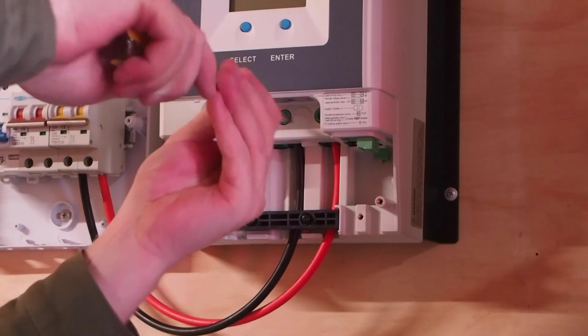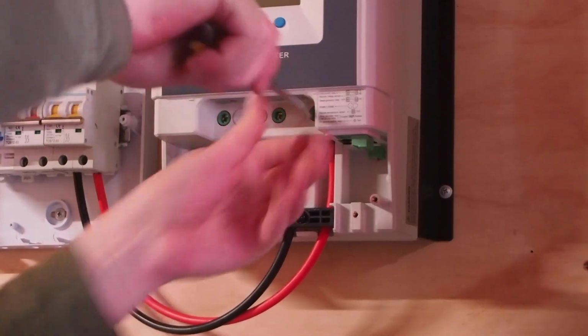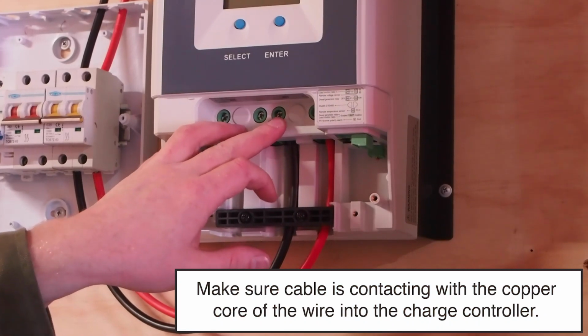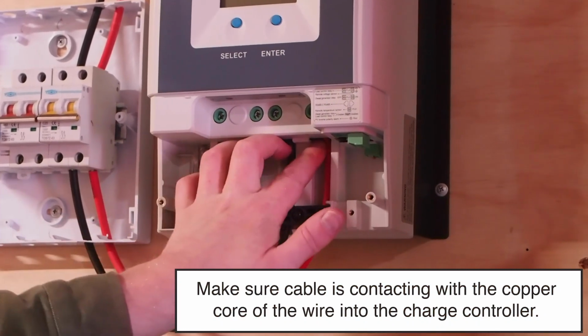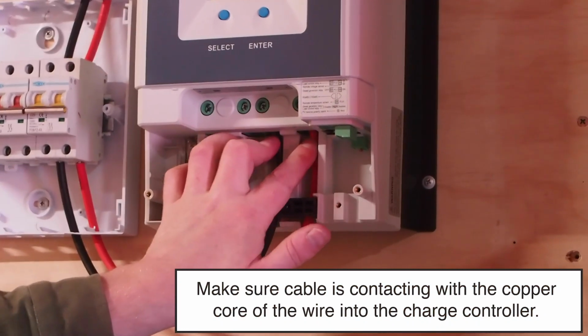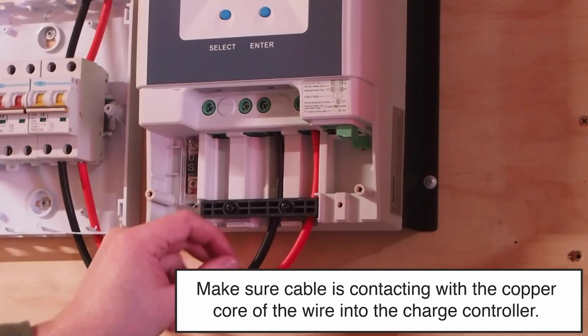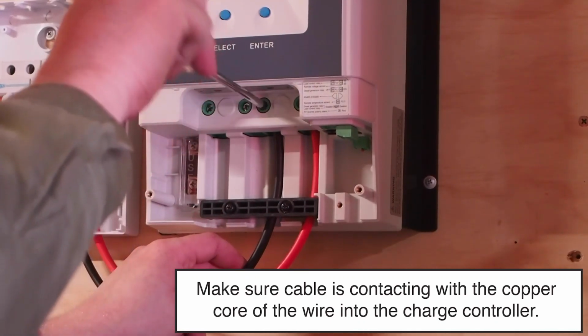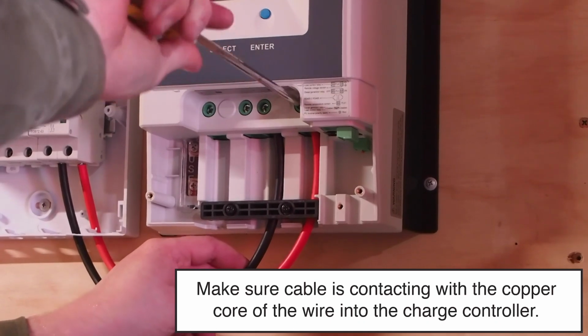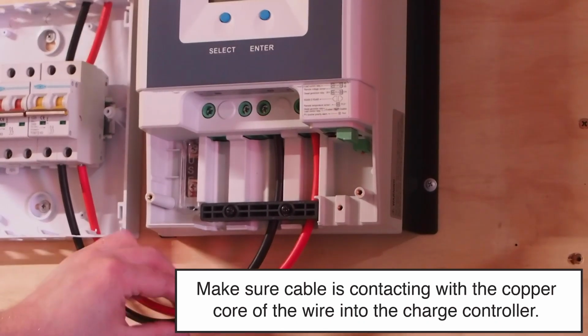Now when you clamp these down and screw these terminals down, you want to make sure that the metal contacts inside these terminals are contacting with the core of the wire, the copper core of the wire. You don't want to be clamping down on the insulation of the cable, because while it might work and you might get a connection, it's never going to be a strong connection and it's only going to cause you trouble.